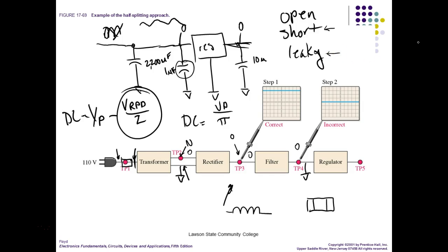When they become leaky, so a capacitor technically, there's no current that passes through it. The current flows in and out of it, right? You understand there's no current that passes through it. It does no electrical work. It does no watts. So a capacitor is not supposed to get hotter than the ambient temperature. If you got a capacitor that's getting hot, then it's bad, right? You understand that? Well, what happens if current starts flowing through it?